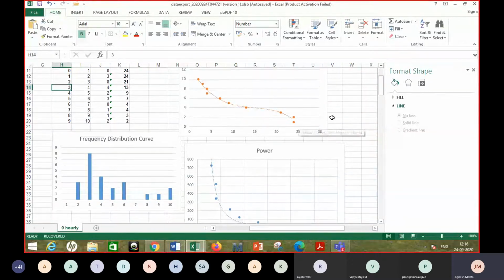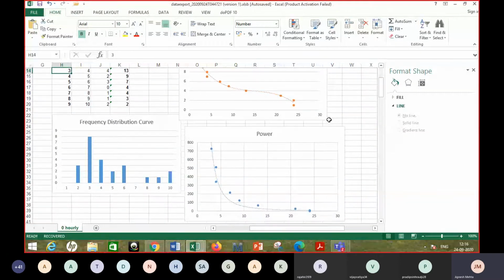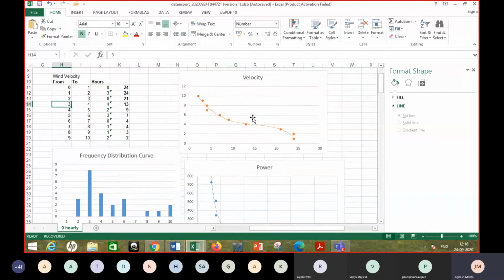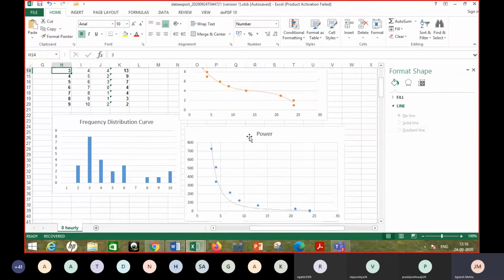Now you may not actually run your turbine for these 11 hours because the power produced is quite low during that period. Even if you, let's say, produce power, it may be just consumed to run the auxiliaries, and you are not effectively producing any power. Then there is no point in running the turbine, right?